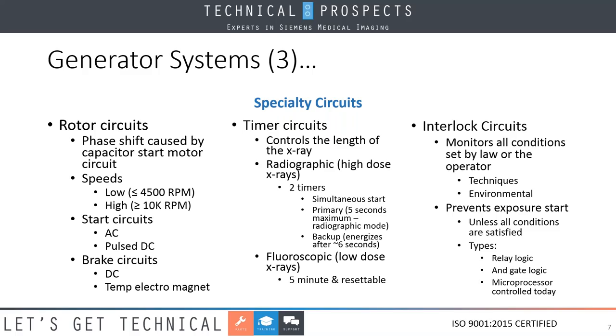Now, the whole purpose of the interlock is to prevent an exposure start unless all conditions are satisfied. Back in the day when I got started in this, we used something called relay logic, and what you would hear would be click, click, click, click, click, click, and every generator had its own sound to it, and that's how we used to troubleshoot. With the advancement of technology, we went to logic gates, and so relay logic now became an AND gate, in which case then we needed all ones saying that something was good in order for us to get the one out for the logic to work. As technology further evolved, now we went into microprocessors. And so now today we're looking at the same thing. We monitor a lot more things. And basically, unless all of these environmental and technique concerns are addressed, we're not going to be able to have an X-ray.